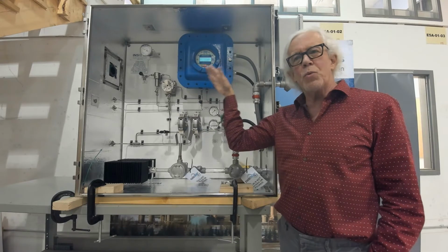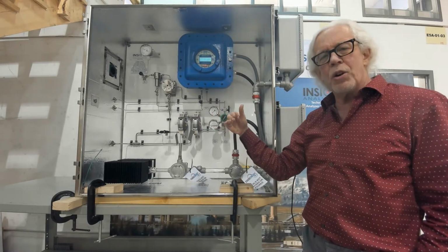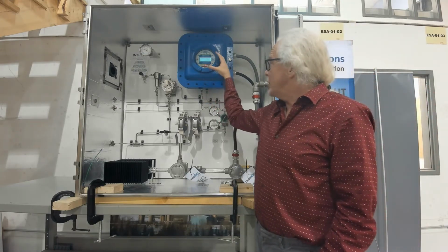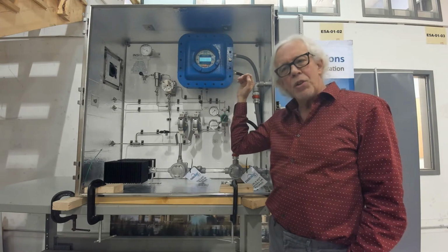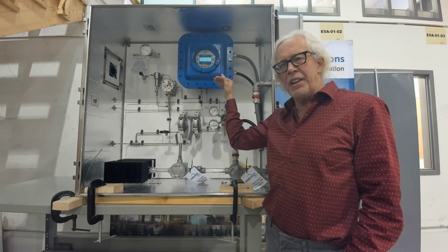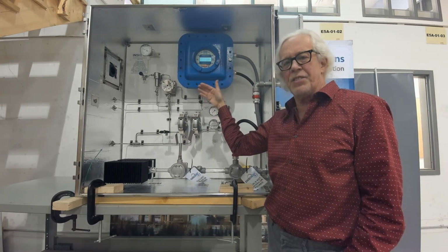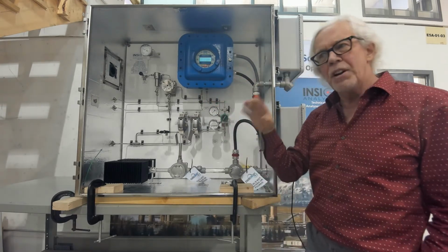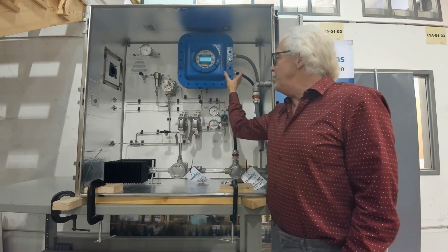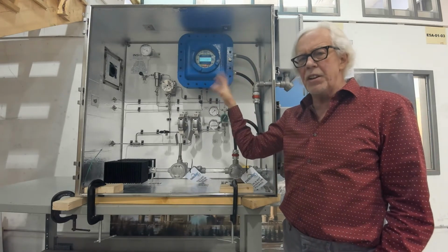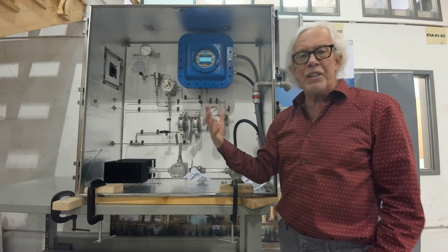Depending on which wavelengths of light that fluid absorbs, we know whether it's water or whether it's hydrocarbons. So we cool that optical surface, watch for condensation, determine which species it is that's condensing, then continue cooling it, and then see the second species that condenses. This allows us to determine both the water dew point and the hydrocarbon dew point, measured at operating pressures for this facility. So this is the actual dew point temperature that would be existing in your pipeline.